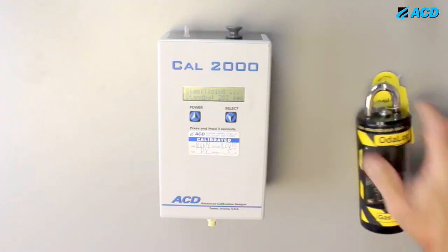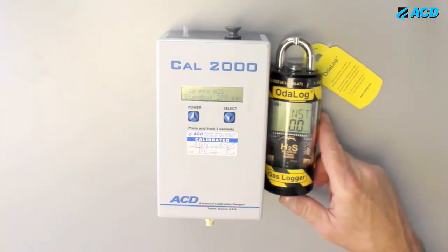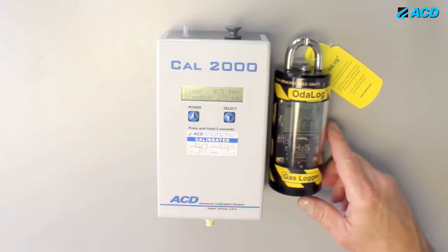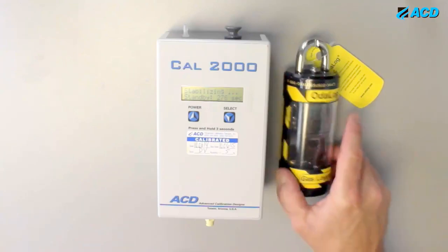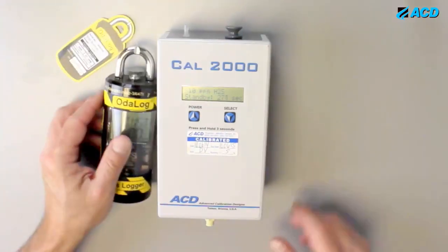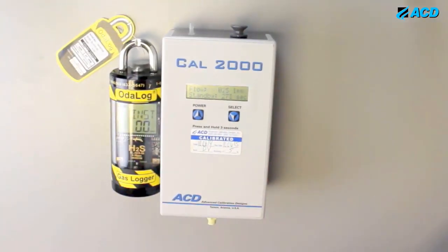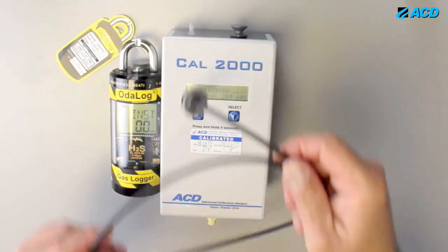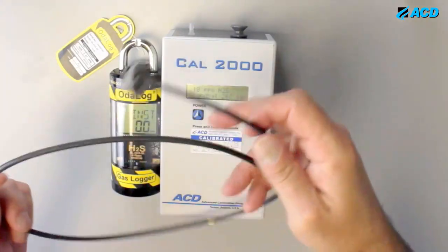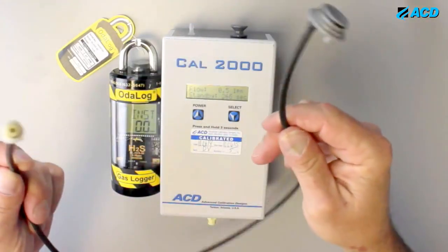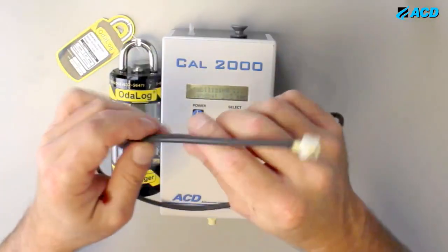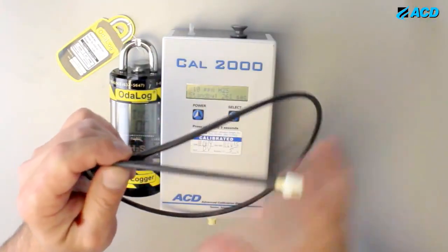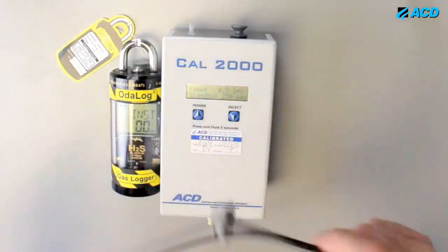Now, let's say we're going to calibrate a diffusion type instrument. This OdaLog right here is a gas sensor that does not have a pump built into it. And this is its calibration adapter. Every Cal 2000 comes with a hose like this. It's Viton tubing with a Teflon lining on the inside, so it's non-reactive. It won't absorb the gas.